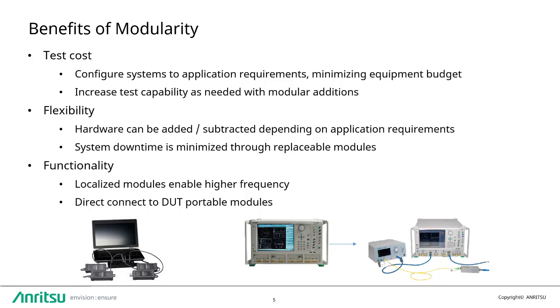Functionality. Some features and capabilities are only available through an architecture that supports modular extensions. Test frequencies into the hundreds of GHz and beyond can only be achieved through external frequency multiplier modules that must be supported in the architecture of a VNA.